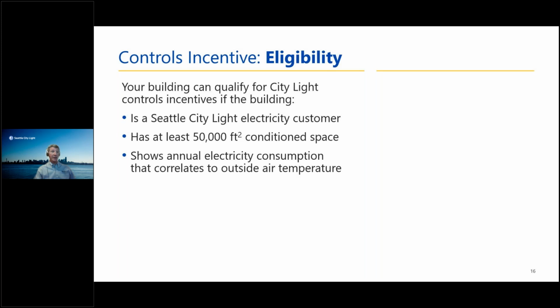We utilize whole building regression analysis to track the energy savings from this approach. This is different from the past, where it's been cumbersome, where often we've tried to make calculations or estimate specific energy savings from specific measures, which takes a lot of time, a lot of resources, and drives up the cost of a project and the amount of time it takes to complete it. But for a building that shows really solid correlation with outside air temperature, we can use whole building analysis to track the savings of the project.